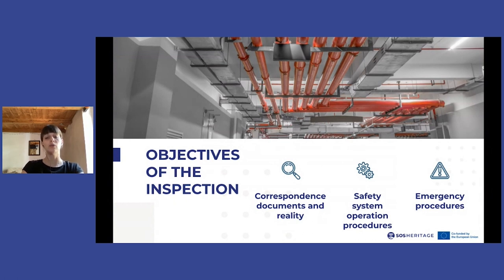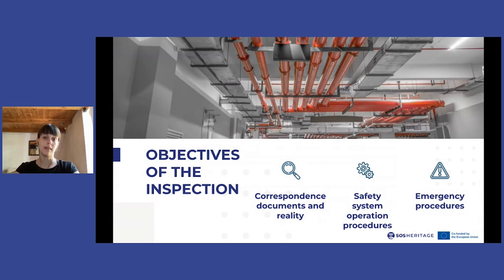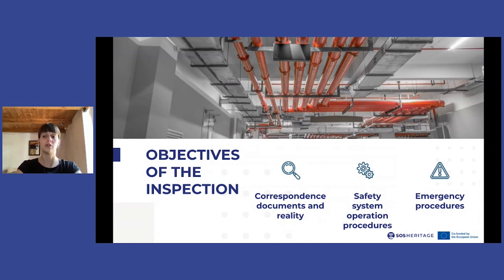It is also useful to identify the actual operation procedures of the safety systems indicated in the plan, including the correct general operation, frequent maintenance of the systems, and the conditions that can compromise the correct use of emergency devices. For example, extinguishers, despite being properly maintained, may be positioned in such a way as to make them practically impossible to reach in an emergency. Or security cameras whose views, even if fully functional, may be covered by boxes or artworks that create hidden corners.